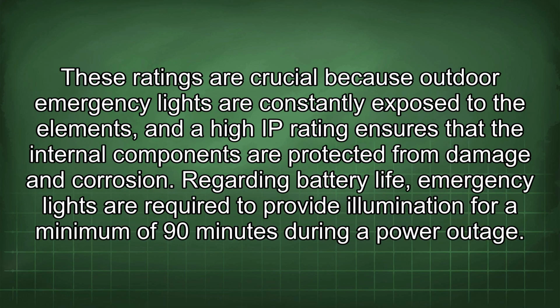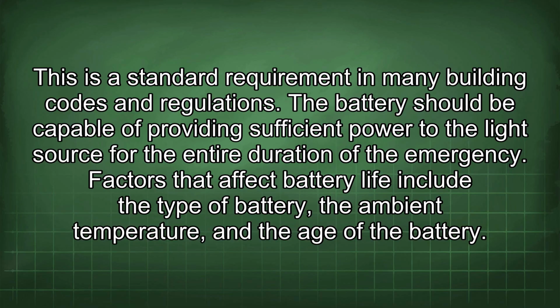These ratings are crucial because outdoor emergency lights are constantly exposed to the elements, and a high IP rating ensures that the internal components are protected from damage and corrosion. Regarding battery life, emergency lights are required to provide illumination for a minimum of 90 minutes during a power outage. This is a standard requirement in many building codes and regulations.